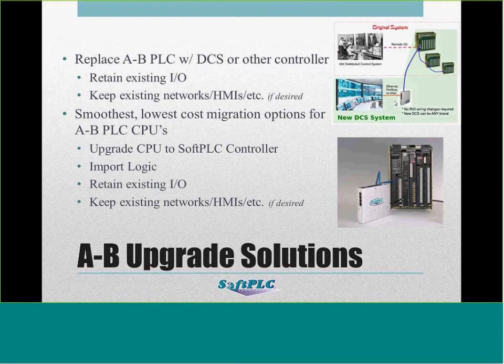On another tangent, we can take the next step. So let's say we put the gateway in and we upgrade the HMI, and now the customer is ready to replace the PLC. The gateway is already an Allen Bradley PLC replacement. We can import the logic from the old Allen Bradley PLC, use the existing I/O, cable to it. Any other HMIs or drives or anything else on the network would not need to be changed, and now we can replace the PLC. So if the Allen Bradley PLC goes bad, if it runs out of memory, Allen Bradley has announced obsolescence of both the PLC 5 and the SLC 500 platforms this year and next year.